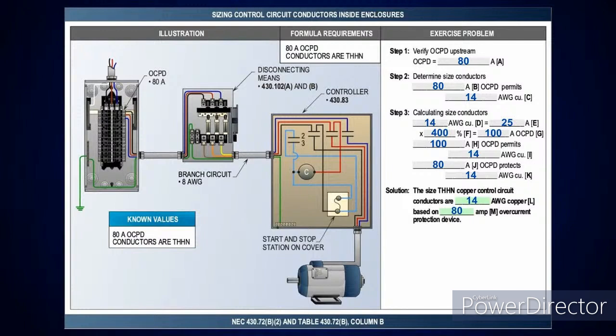So my overcurrent protection device upstream is 80 amps, and 80 amps will permit a number 14 conductor. Now, in order to prove that point, a number 14 conductor is good for 25 amps per table 310.17. Then it tells you down in the note to take that at 400%, and that'll give you 100 amps. And they're telling you 100 amps would be permitted on the 14 conductor. Therefore, that 80 amps is permitted because it'd allow you to go all the way up to 100 amps. See there? Right. So it's establishing the fact even further.